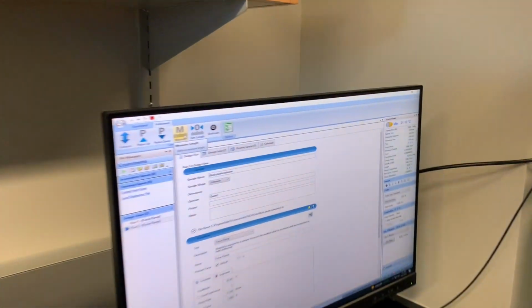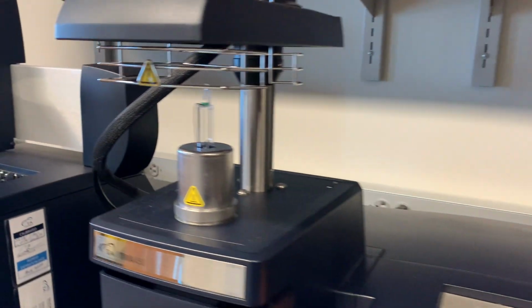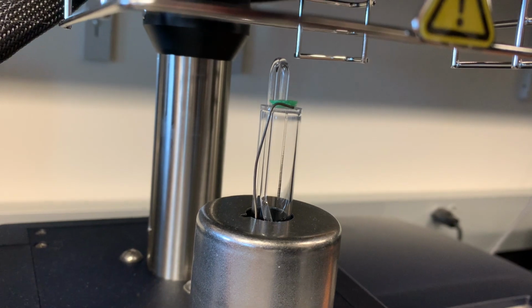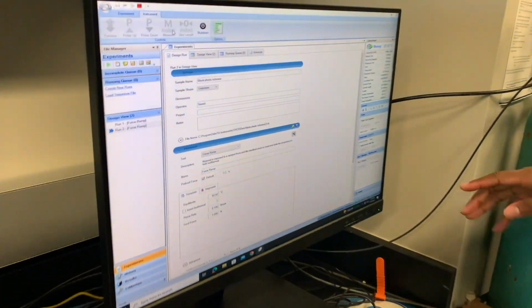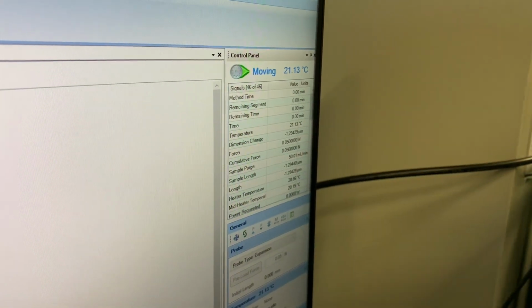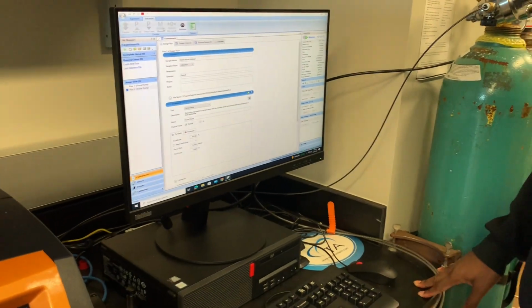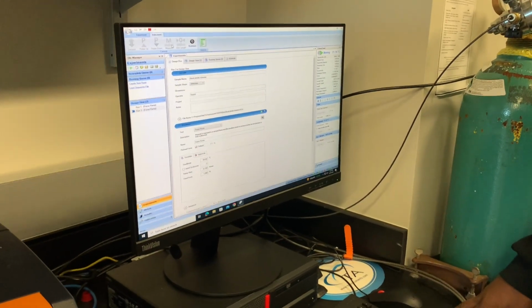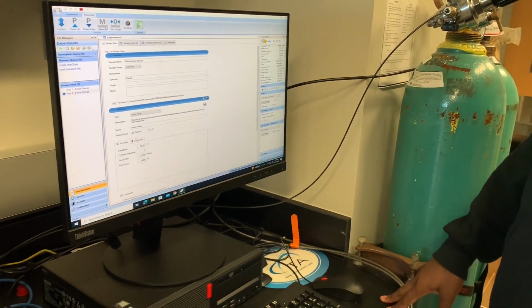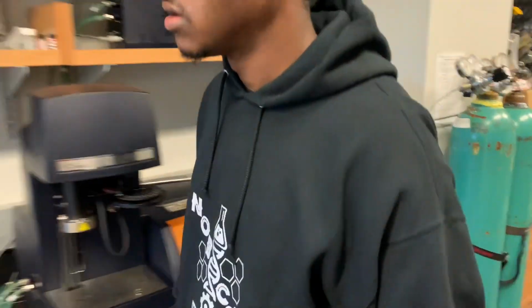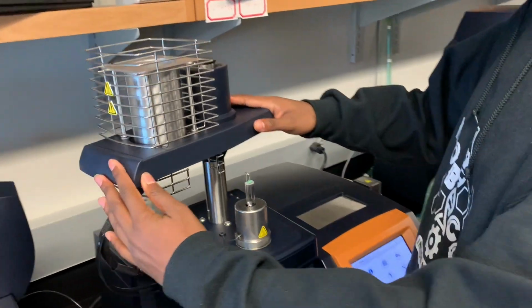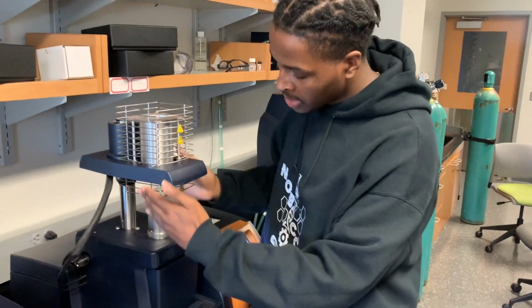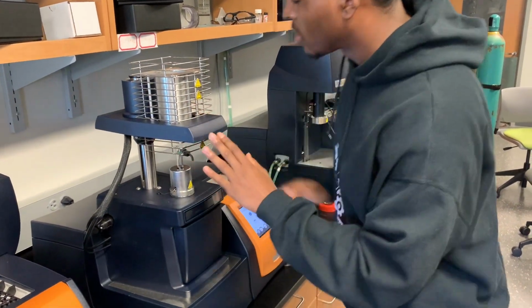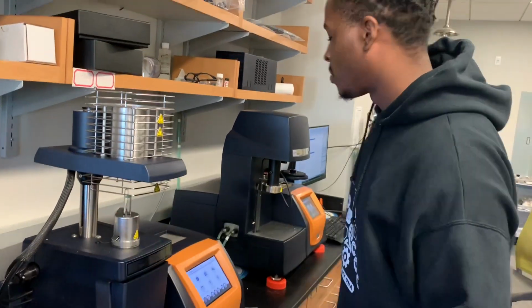Once your sample is lined up, you're going to go back to the software and hit measure. This is going to measure out your sample. On the side it shows you your dimension change and basically the dimensions of your sample. Now you want to make sure the furnace is facing like this, so it can come down onto the probe. If it's like this, you can just move it to right here. Now that your furnace is lined up with your probe, you're gonna hit furnace down.